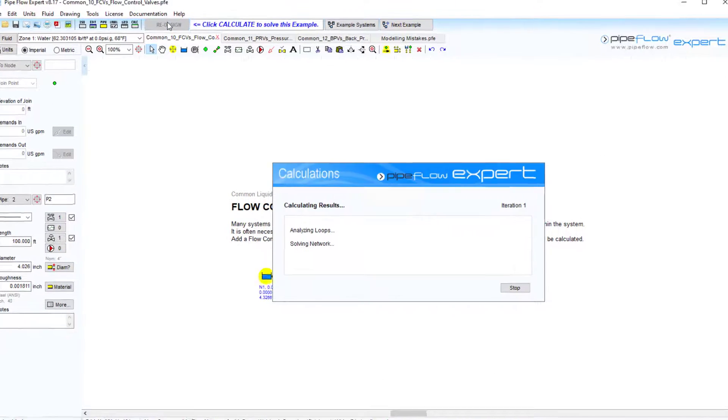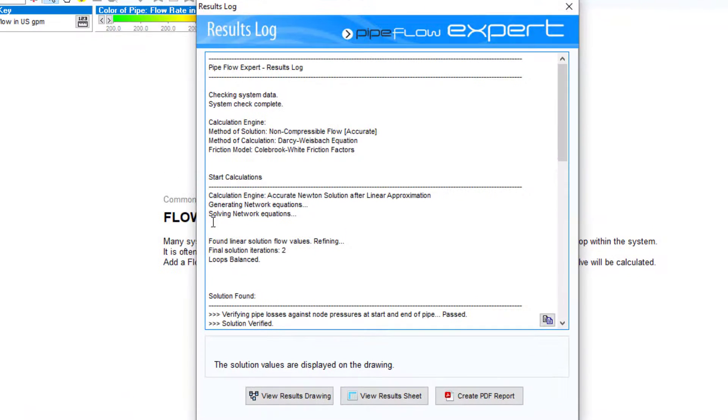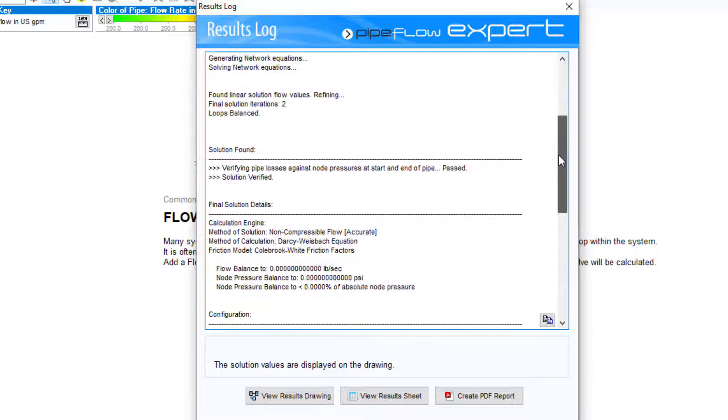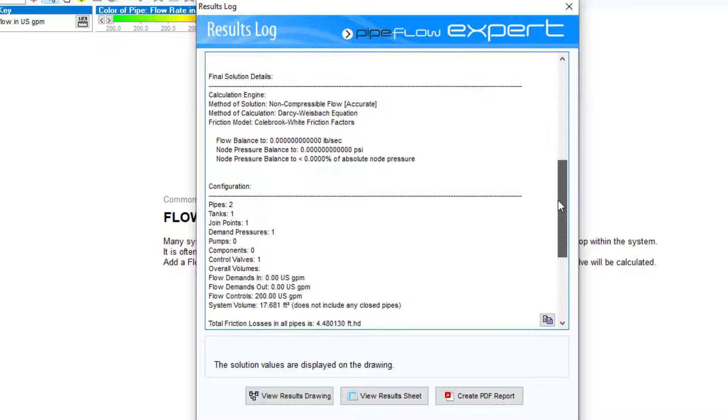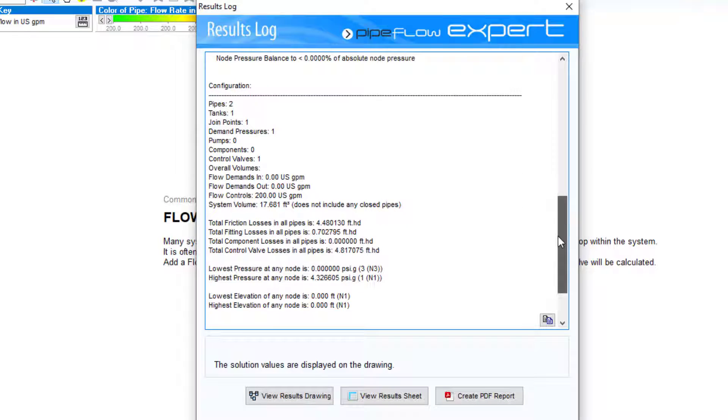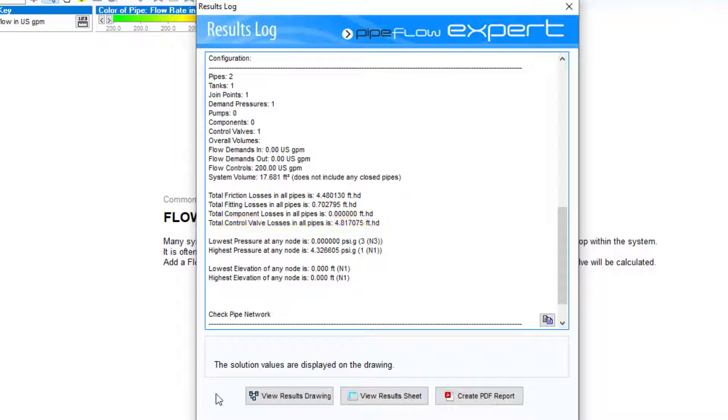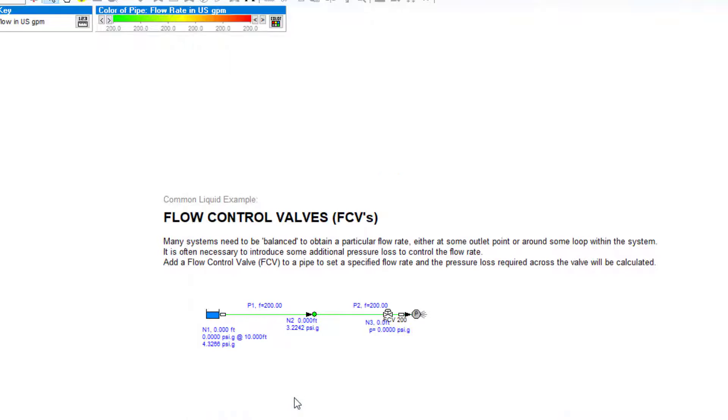The software will calculate the additional pressure loss introduced by the flow control valve to limit the flow rate in the pipe to the value we set. The pressure loss across the FCV is reported in the results log here and can also be viewed on the results drawing by hovering over the valve, where an equivalent CV or KV value is also given.